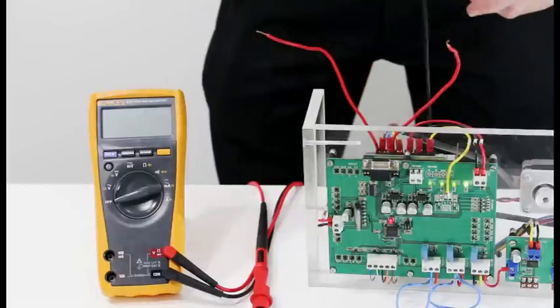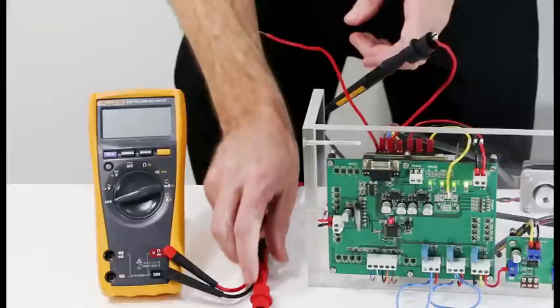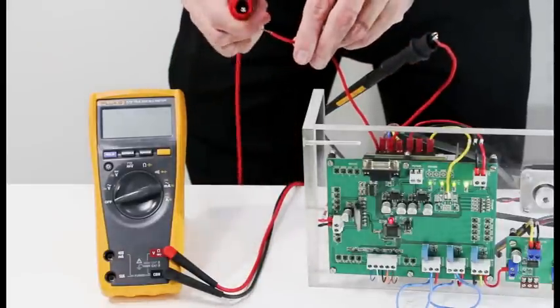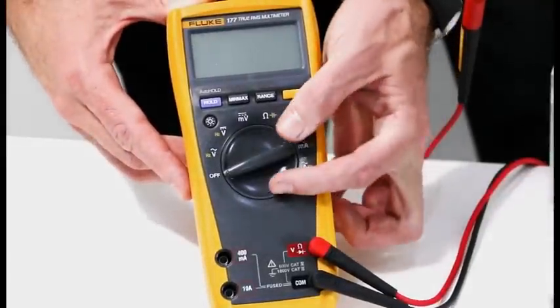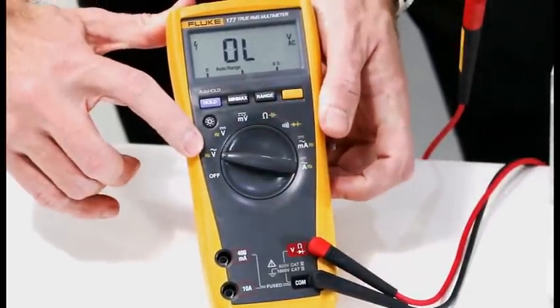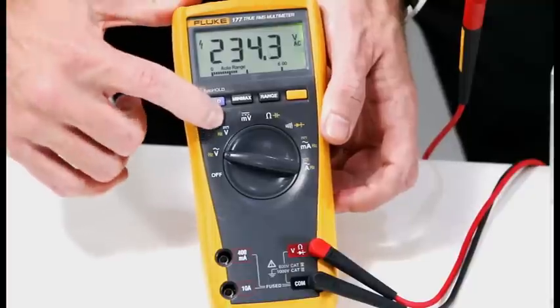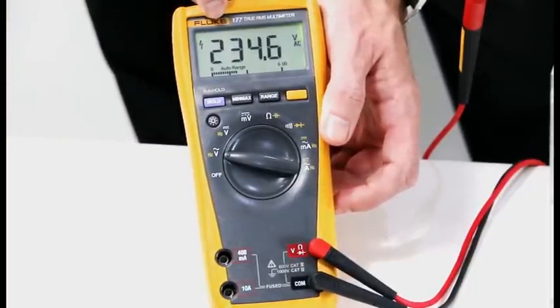I take my black test lead and connect it to my neutral wire. I then take my red test lead and connect that to my live wire. I now take my rotary dial on my Fluke 177 and turn it over to the voltage AC side. If you look here you can see I'm measuring 234 volts AC.